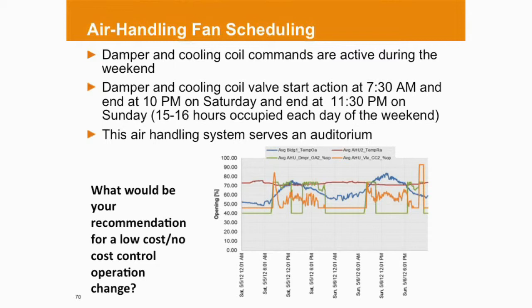So what can we do about this? We see a lot of outdoor air economizer. We see a lot of cooling going on. The fan's obviously running. Base it on CO2, I mean, that's a big thing. If CO2's down, why bring in outside air? Now, would you also base the fan operation on CO2, or would you shut it off? You base the fan on occupancy, if you know what your schedule is, but a big thing is close outdoor air dampers.